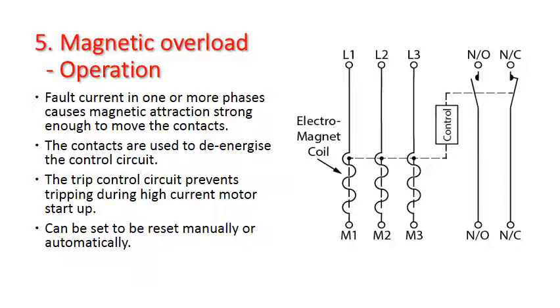So how the magnetic overload works: it has three sensing coils that sense current. As the current increases in the circuit to a level that is dangerous to the motor, the magnetism developed then operates the contacts via the control circuit.